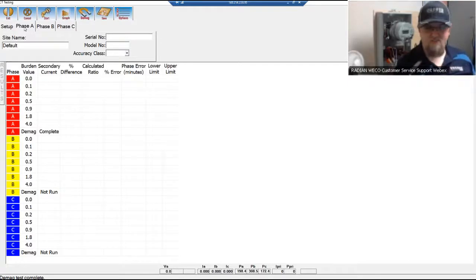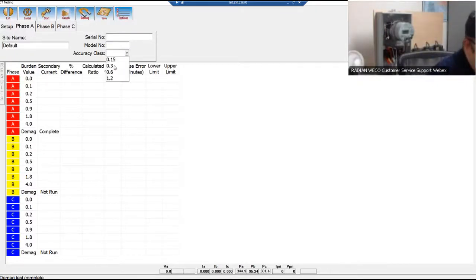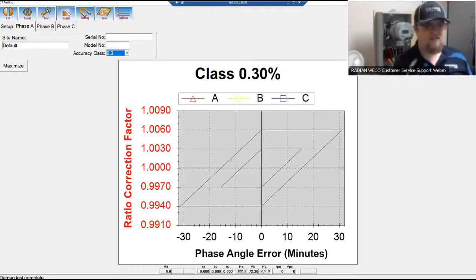Moving over from the Setup tab to each phase A, B, and C, this is where you can track information on the CT that you're testing. You have phase A, phase B, and phase C, and each one needs a serial number, model number, and accuracy class. Serial number can usually be read off the faceplate of the CT. Model number is associated with it if you have an ABB, RIB, CT, something like that, that has a model number tied to it. If you want to track that, you can put that in the model number field. And then accuracy class of the CT, which also drives the graph that I showed previously. So if I change the accuracy class here to 0.3, my graph is now a 0.3 accuracy class graph that I can show off later.